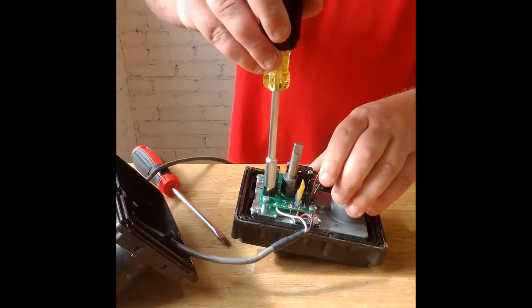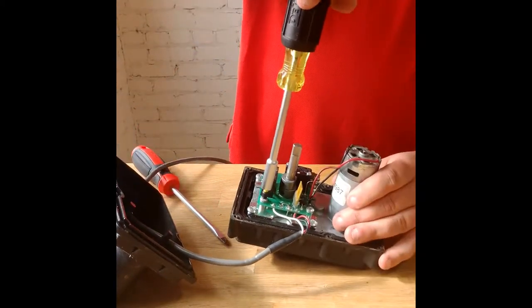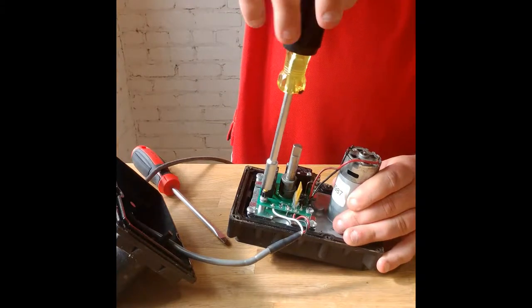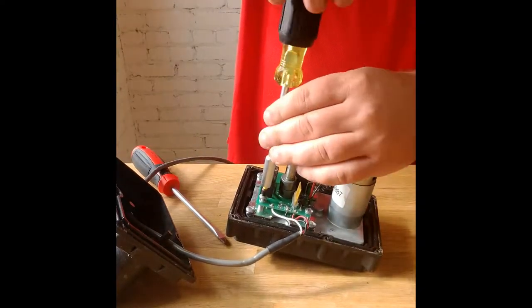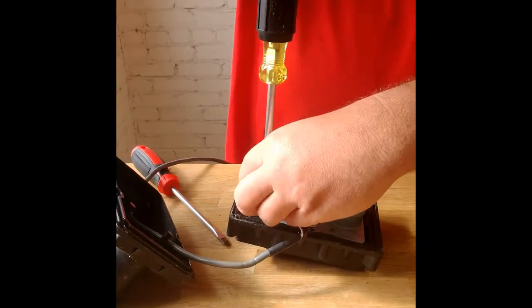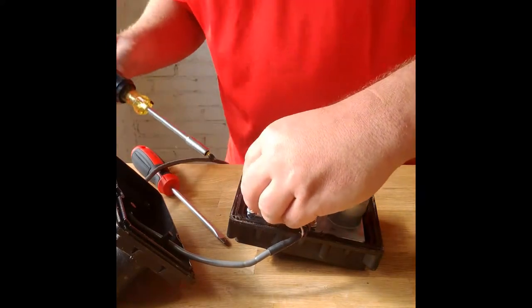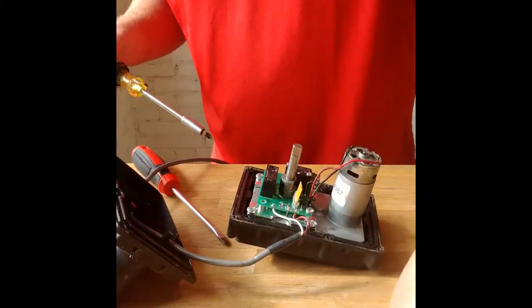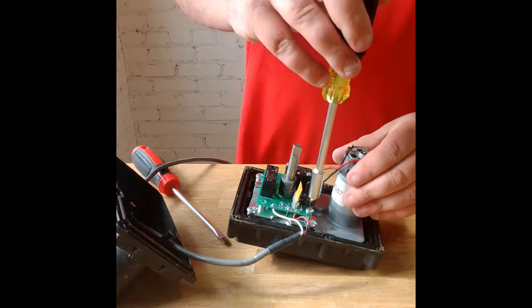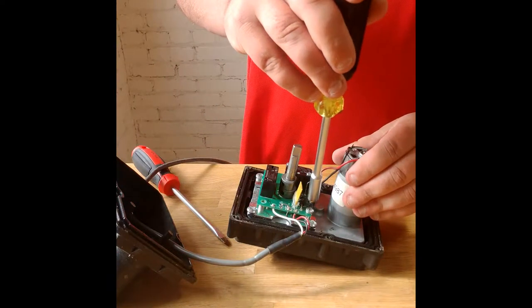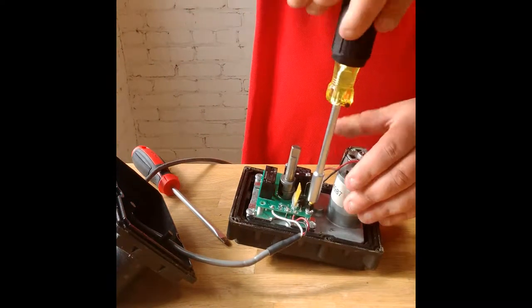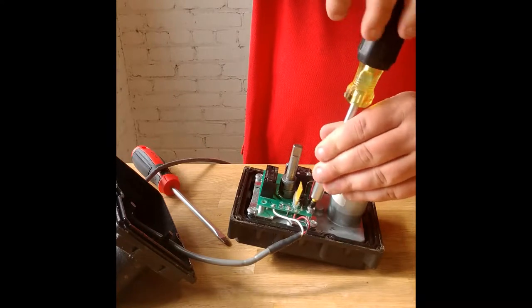Again, the usual culprit is those relays go bad. That's really the first thing that goes bad. You can replace it four to five times before you need to replace the switches or the motor itself. So they actually have quite a bit of lifetime to them.